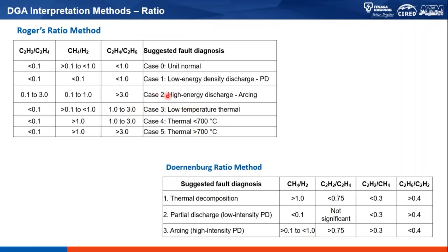You can also see the C2H2 over C2H4 ratio is also being used by Rogers ratio. So both Doernenburg and Rogers ratio use the same ratio, for example, acetylene over ethylene. But as you can see, the suggested faults are different based on the limits given in this table, or the code used by the Rogers ratio method, whether or not it satisfies the code given for a particular fault diagnosis.